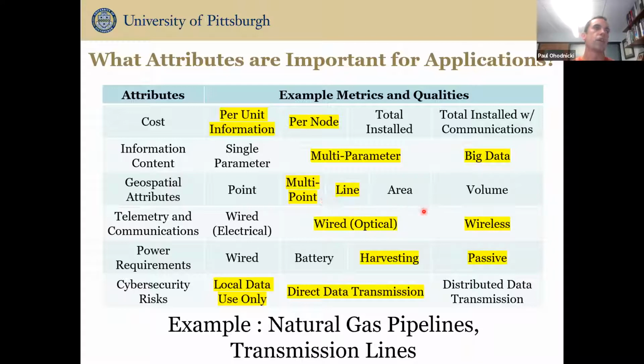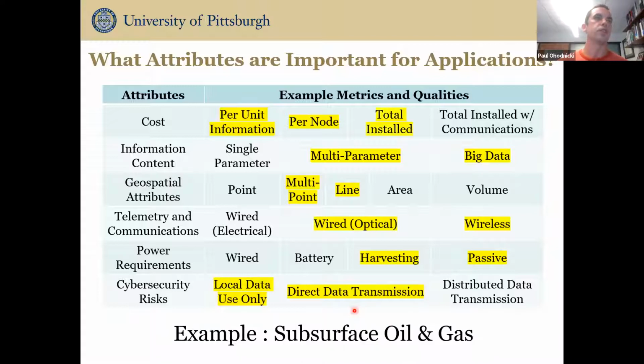In terms of telemetry, we don't want to be running a wire along a pipeline or transmission line if we don't have to, so either optical-based wired approaches, meaning optical fiber, or wireless-based approaches are preferred. From a power perspective, we'd prefer it to be passive in almost all cases. In terms of cybersecurity, because with a pipeline or transmission line we're typically taking information measured all along the length of the system and accumulating it, we may have direct use of that data in some central station, or direct transmission along the length of the system. This impacts the total cybersecurity risks we'd have to be concerned with.